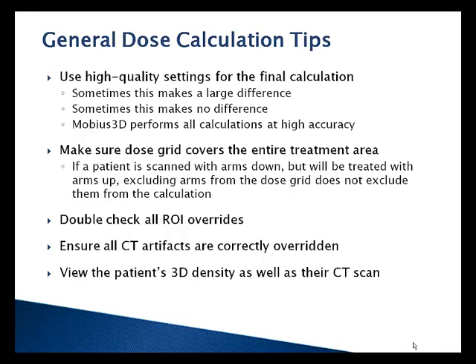The other big one we've seen: make sure the dose grid covers the entire treatment area. This is important because sometimes you'll find out that the dose grid in your planning system isn't doing quite what you expect. If you scan a patient with their arms down, but you plan on treating them with their arms up, we've seen some people draw the dose grid around just the torso. And then in your planning system, you'll see dose just in the torso. And then you say, okay, great, I'll tell my patient to put their arms up, and we'll treat them like that. That's not actually how that's working. Your planning system is still using the arms to attenuate the beam. If you send it over to a system like Mobius 3D, you'll see enormous failures in the arms, and you'll call us up and say, why is your system wrong? And we'll say, no, that's how your planning system's calculating dose as well.